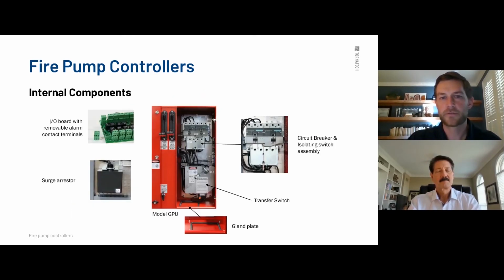So two screens are not required on our panels. The internals of the transfer switch, it is the same circuit breaker and isolation switch. We have the same removable alarm contacts. We have another surge arrestor. And also another gland plate because you also have to run the wires into that. And again, we prefer you to go through our gland plate.